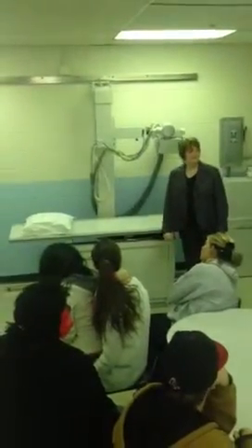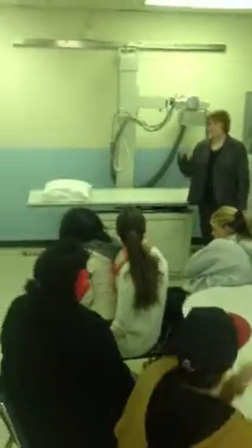Okay, and at the fluoroscopic unit, at the tabletop, X-ray intensity at the tabletop for upper GI exams, regular fluoroscopic procedures, how much X-ray intensity will you have? Maximum, not 20, but 10. 10 roentgen per minute. And then what about if it's high-level control like angiography? 20. So 10 versus 20: high-level control is 20, regular is 10.